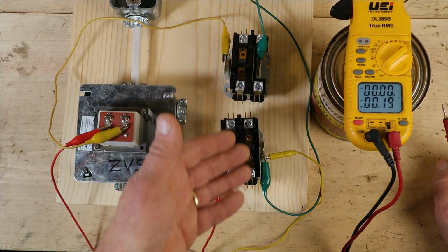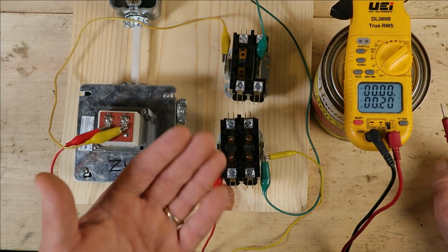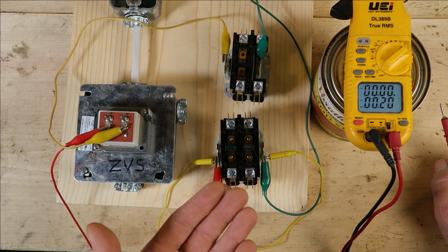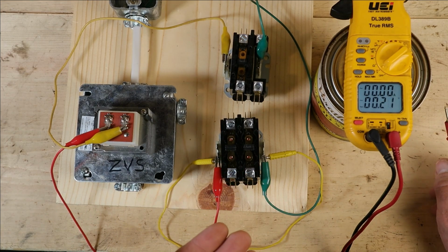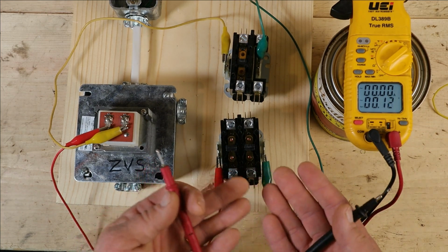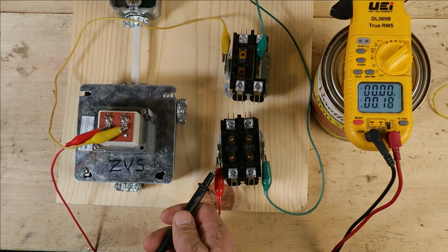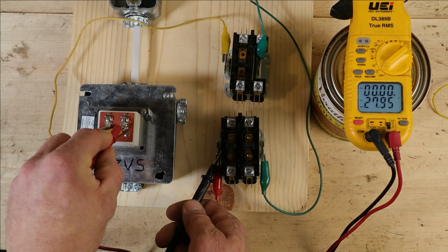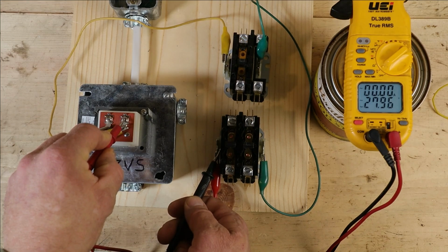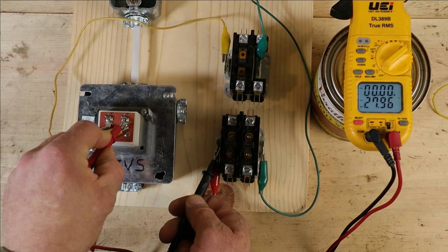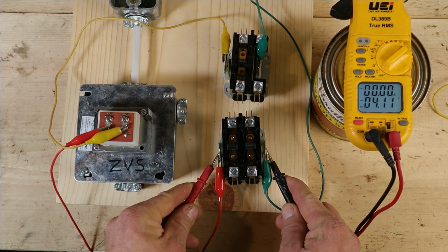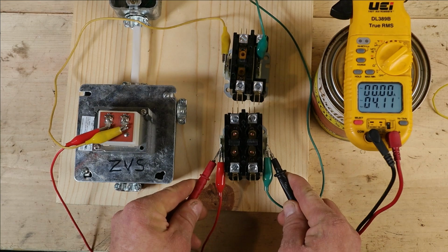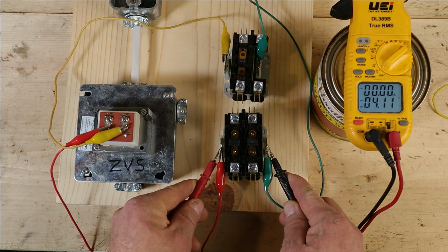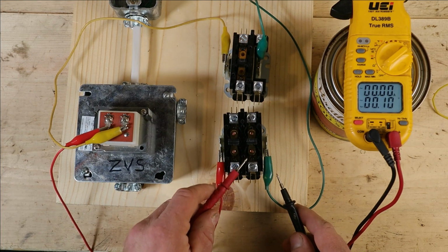When we take our resistance readings on these coils individually, we get 12 ohms, 17 ohms, 1000 ohms. That's not really telling us if there's a problem or not. What's really telling us is the voltage drop across that component. If you have a voltage drop across a coil, you can test the actual voltage coming into the coil to see what you have. As you can see here, I have 28 volts coming into my first coil, even though it's not closing. But when I measure across the coil, I'm only reading 4 volts. That tells me I have another point of resistance in this circuit that is higher than the resistance of this coil, and that is absorbing most of the voltage, not leaving me enough to operate this contactor.